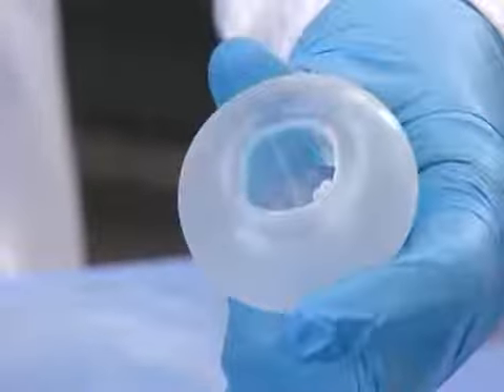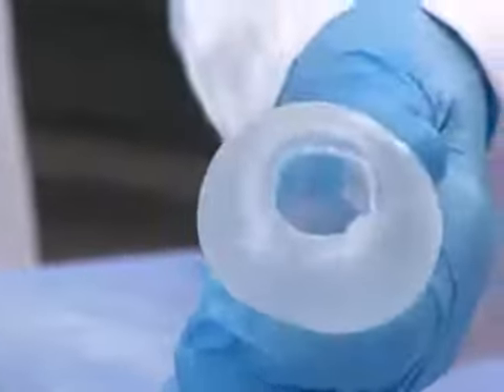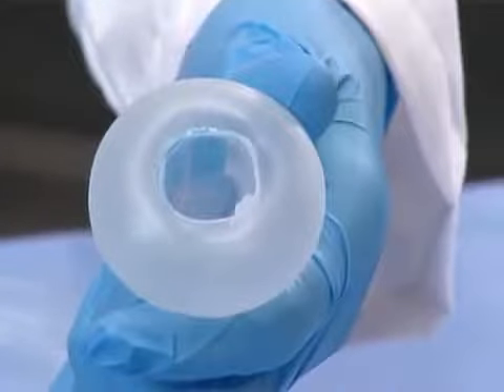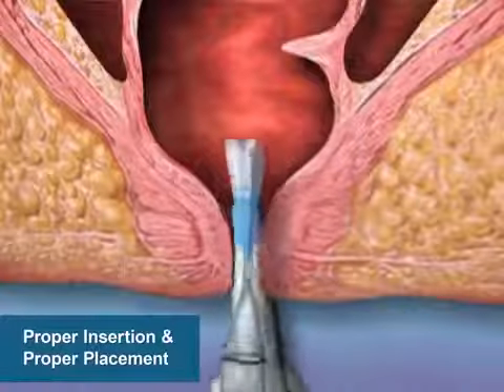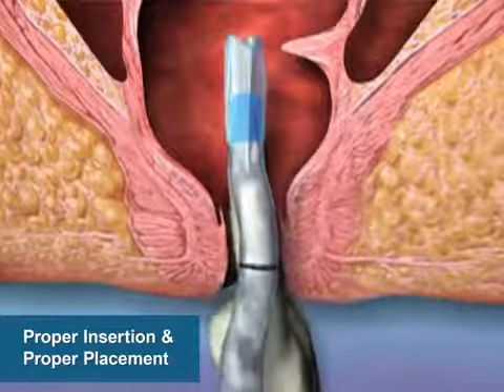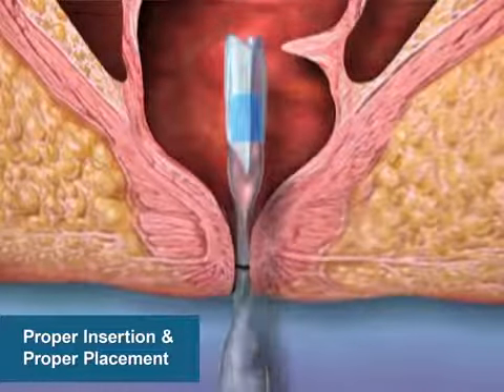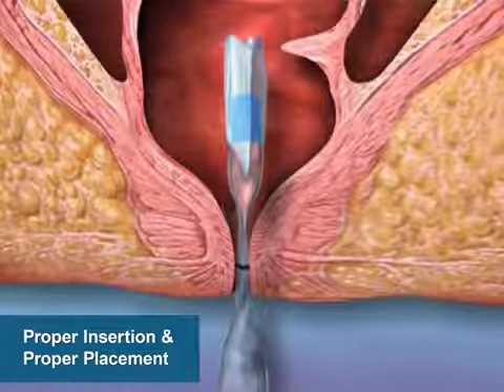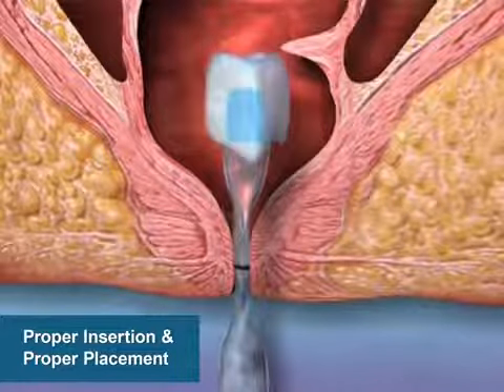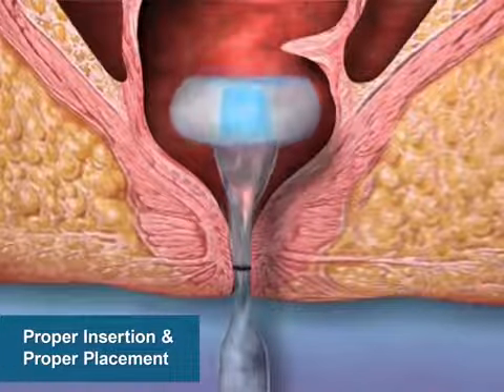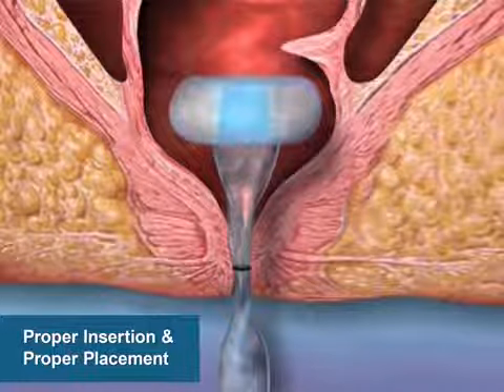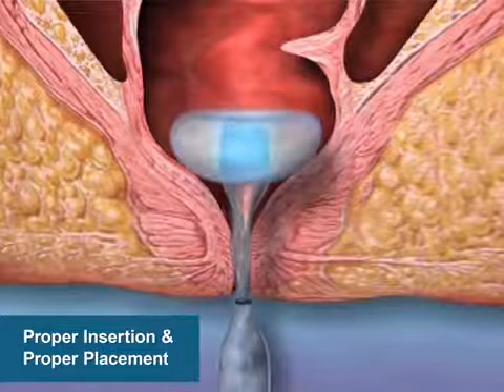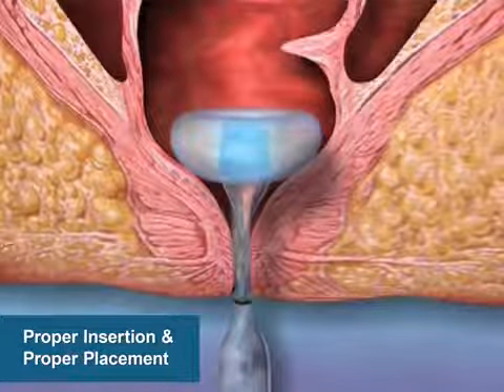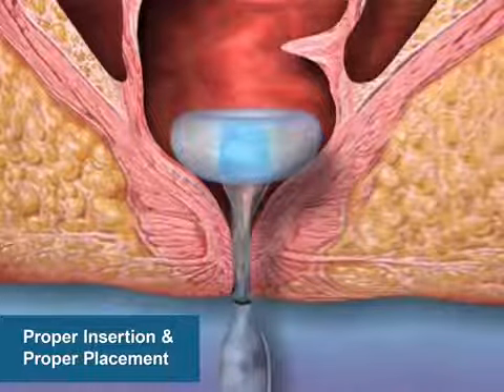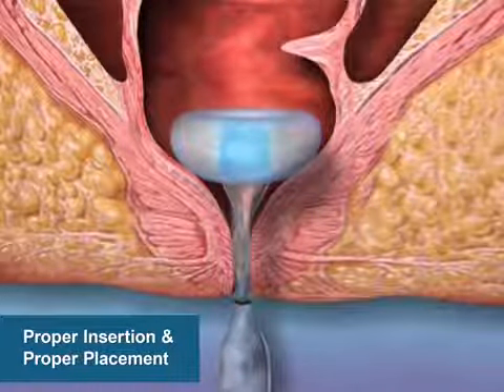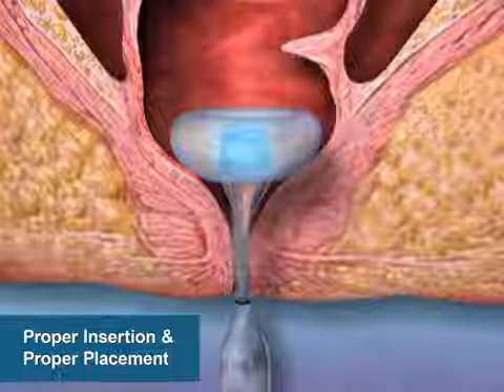The soft, flexible, low-pressure balloon is designed to help reduce the risk of tissue necrosis. Once inserted and inflated to the optimal volume, as shown by the indicator, the retention balloon conforms above the sphincter anatomy on the rectal shelf to create an effective seal to minimize leakage and to safely divert and contain stool. Once in place, the drainage tube collapses to an 8 mm diameter, helping to minimize the impact on sphincter tone.